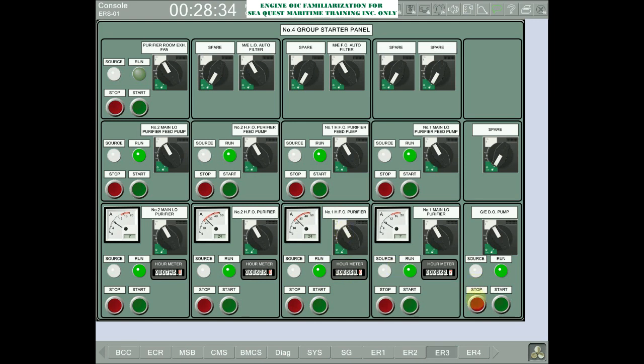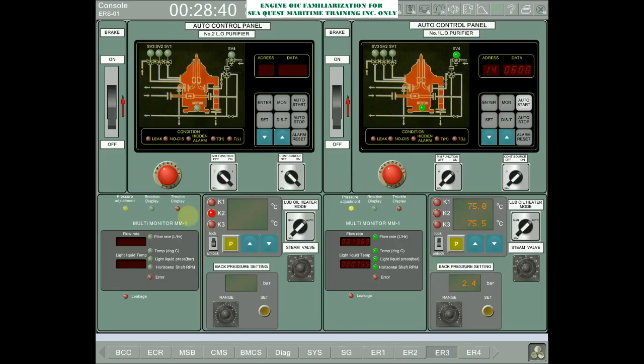Okay, now let's go to lube oil purifier 1, 2 LOP. Switch on the monitor and control source selector knob. Then monitor from the multi-monitor screen the RPM of the number 2 bowl. Once it reaches about 10,000 RPM, then you can press the auto start button. So that's already 10,000 RPM, so we can press the auto start button.